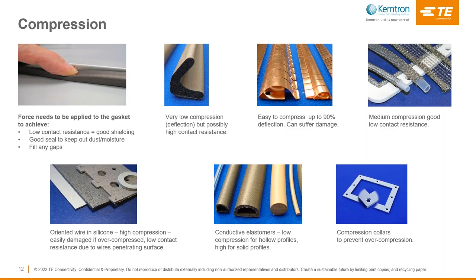Different types of EMI gasket require different levels of closure force. For cabinet doors requiring several metres of gasket strip, a very low compression force gasket will be required unless the cabinet is of robust construction and the door is hydraulically operated. Conductive fabric-over-foam lip seals offer the lowest compression force. Beryllium copper fingers can also be very easy to compress but can suffer damage through snagging and broken fingers. Sponge or hollow tube type gaskets such as knitted wire over a rubber core offer medium forces. Solid silicone rubber seals loaded with conductive particles or wires will be the hardest to compress but also offer a good dust and moisture seal.